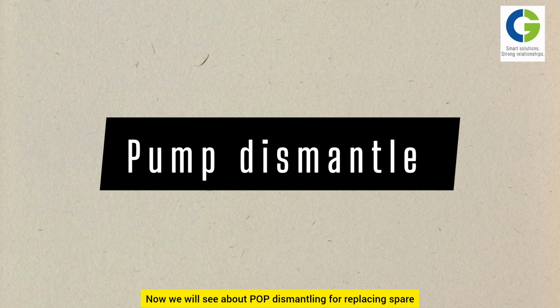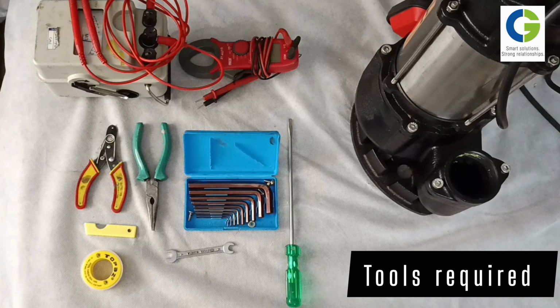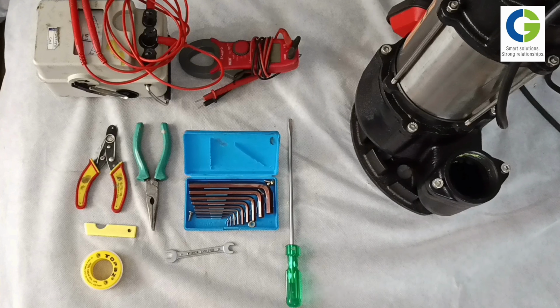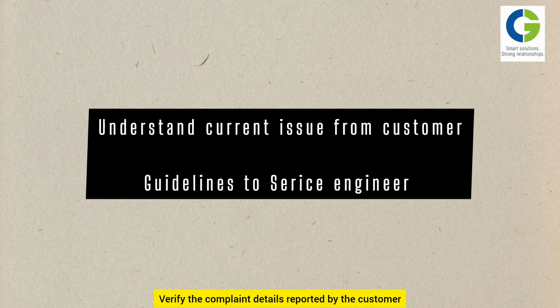Now we'll see about pump dismantling for replacing spares as well as for service purposes. Before visiting a site for installation or service, ensure you have all these tools: clamp meter, megger, Allen key set, MRF tape, insulation tape, nylon hammer, screwdriver, bearing puller, or any other necessary tools. First, understand the issue. Verify the complaint details reported by the customer. Check whether the product is in the warranty period or beyond it, based on the purchase invoice or warranty card. Note the serial number for further reference.